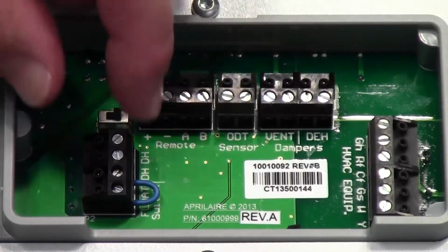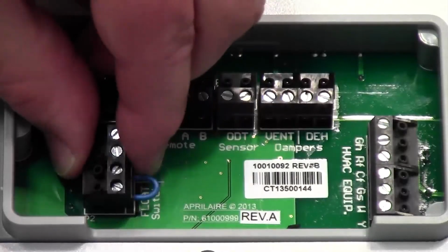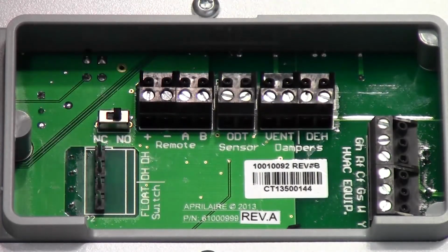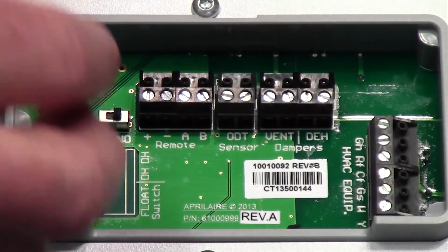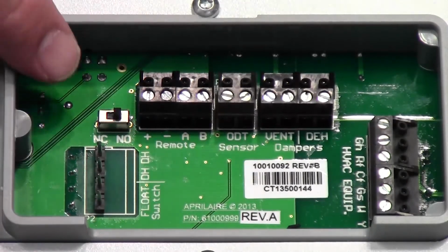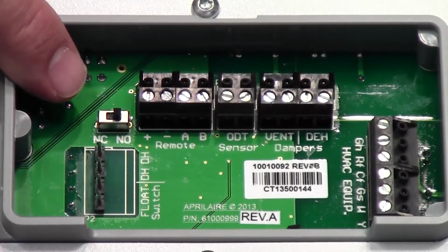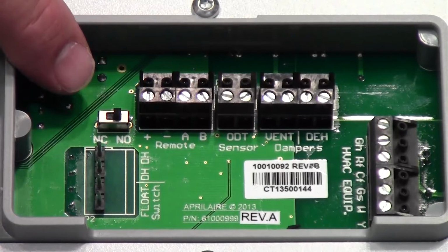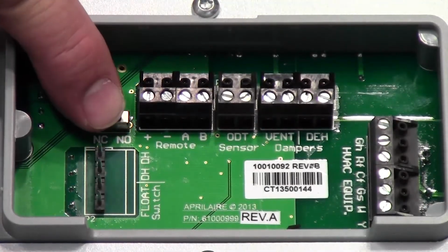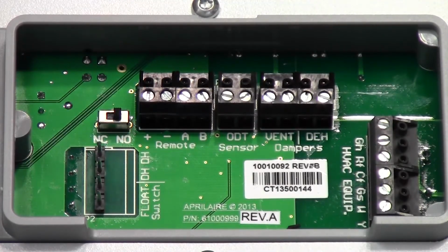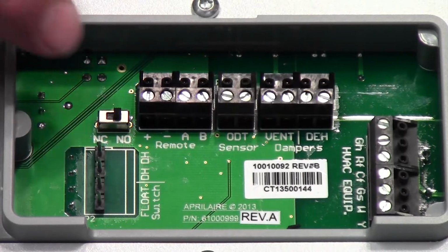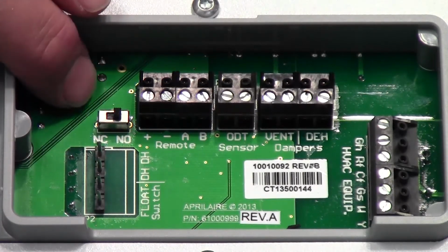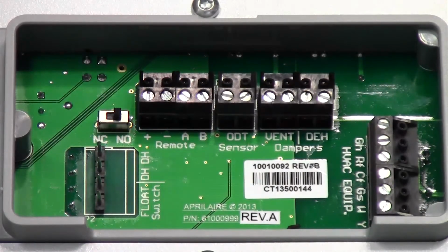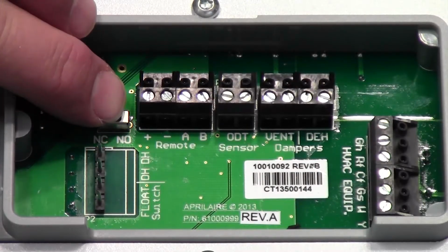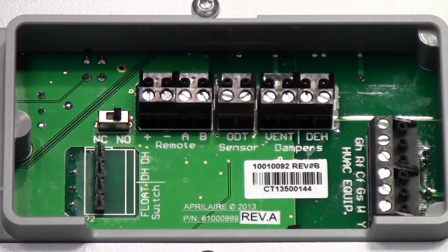On the circuit board here, the wiring terminal blocks are removed to make it easy for the installer to get the wires in and then plug them back into place. As you can see, we removed all the dip switches that we had on our other units, and we have one switch here, and that NO or NC is for normally open or normally closed contacts. That's for control options. There's 1 or 2 companies out there that have a control that uses a normally closed contact. Everybody else like us uses a normally open. So that's the only switch left.